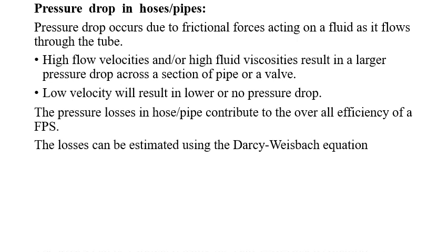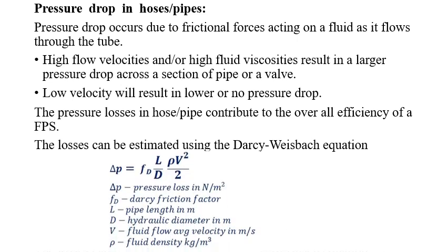The losses can be estimated using the Darcy-Weisbach equation: ΔP = f_D × (L/D) × (ρV²/2), where ΔP is pressure loss in N/m², f_D is the Darcy friction factor, L is pipe length in meters, D is hydraulic diameter in meters, V is the fluid flow average velocity in m/s, and ρ is fluid density in kg/m³.